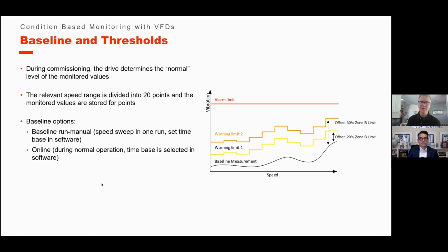And it's like artificial intelligence. It sits in the background and keeps gathering the data as you go up and down through that process in the speed range and develops a baseline from that. So very unique. So you can cover both sides of that spectrum, which is really great for the software. Once you develop that baseline, you have thresholds. And these thresholds are what you determine.